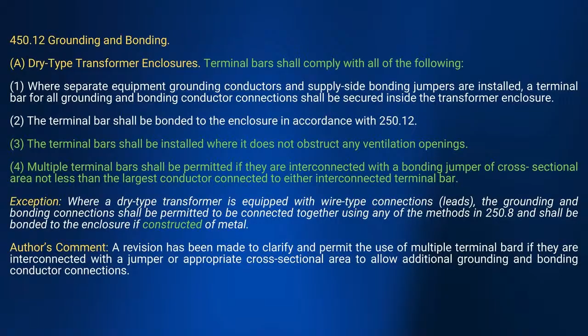One thing I like here is they talk about these terminal bars and require them to be installed where they don't obstruct any ventilation openings. And if you have multiple terminal bars interconnected with a bonding jumper, the cross-sectional area can't be less than the largest conductor connected to either interconnected terminal bar. So they're just clarifying that to make sure you have the space to do what you need to do.